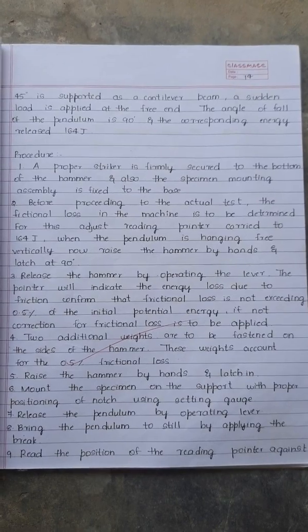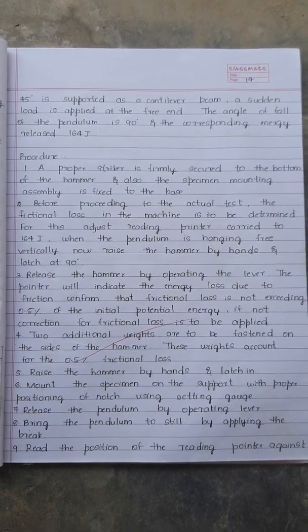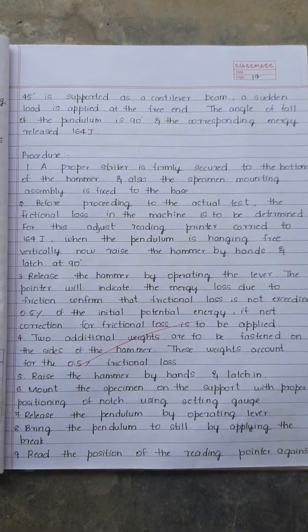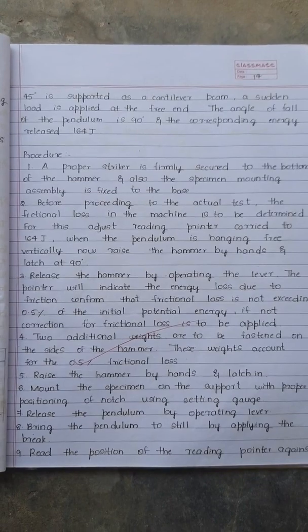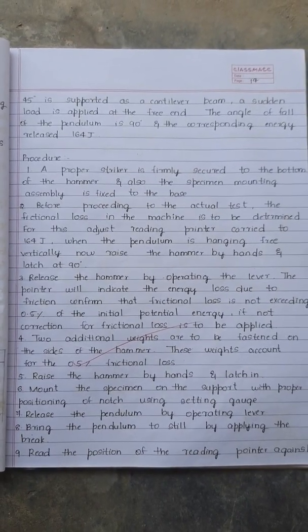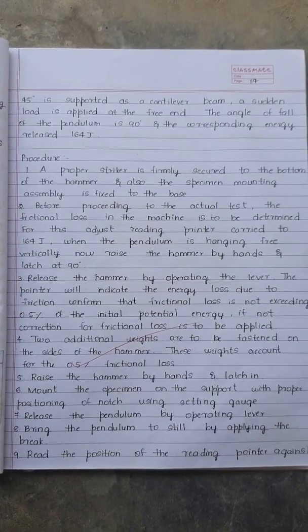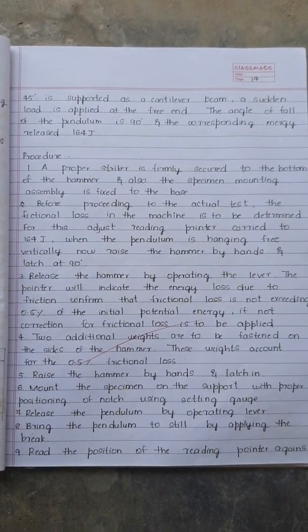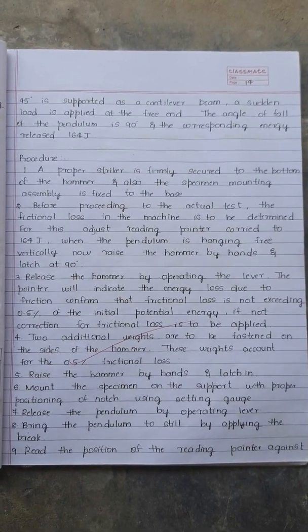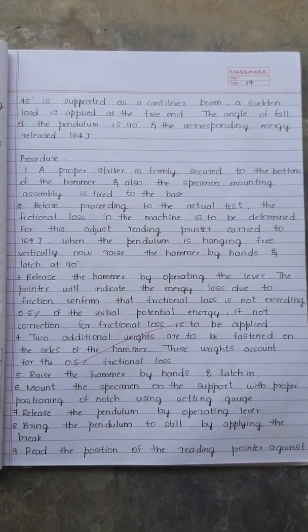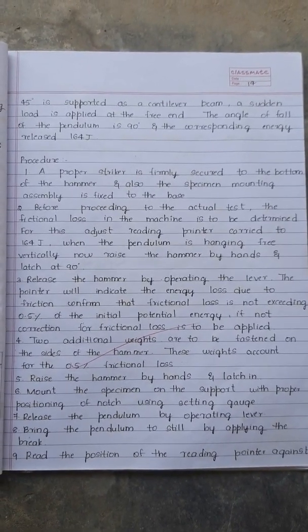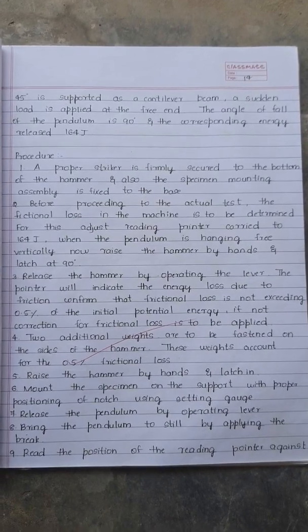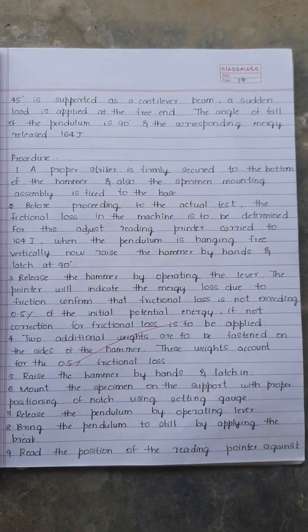Raise the hammer by hand and latch it at 90 degrees. Release the hammer by operating the lever and the pointer will indicate the energy loss due to friction. Confirm the friction loss is not exceeding 0.5% of the initial potential energy. If not, correction of friction loss is to be applied.